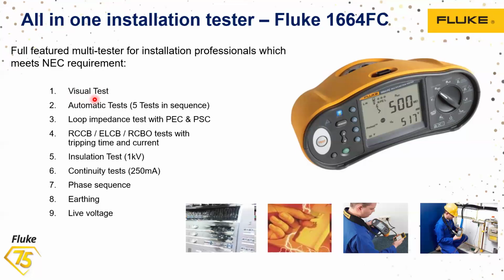Why a visual test? Before doing any test, we have to check the electrical installation for any burning marks or burning signs, any melted wires, loose or damaged connections, tripped breakers or blown fuses. Also you have to monitor the temperature, listen for any abnormal noises, and look for damaged cables, that is, damaged insulation. Most of the time, just doing the visual inspection, you can identify some of the problems before you actually carry out the test. Next is the loop impedance test.